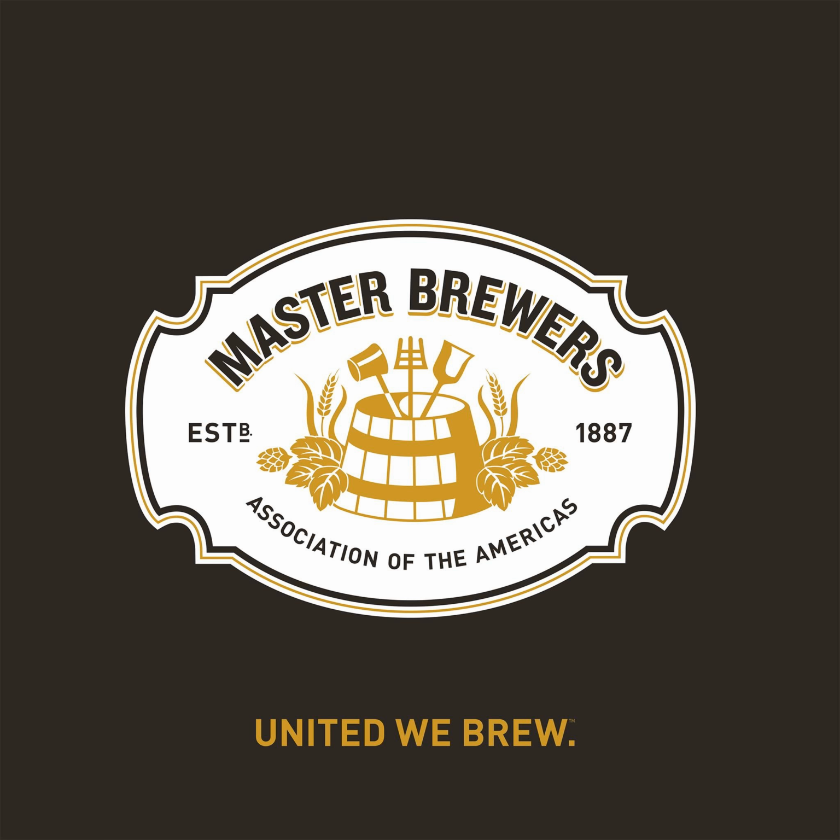Okay. The set point is something that a lot of times we understand when we're using a chiller system that the lower we can make that temperature of the set point is going to give us a bigger temperature difference between what we're working with in the brewery. For example, if we're trying to crash a tank from say 70 down to 32, I've had people ask, well, can I operate my set point at 20 degrees Fahrenheit as opposed to 28 degrees Fahrenheit to try and get a little faster pull down.